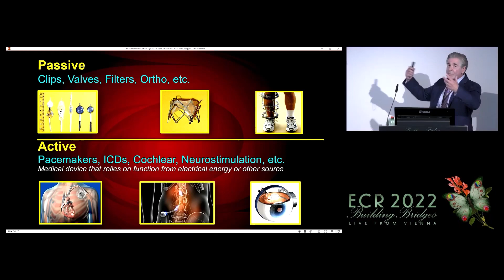So these are the factors that impact passive implants when you're scanning with vertical field MR systems. First and foremost, we need to give attention to the field strength. So is it 1.2 Tesla or is it 0.2 Tesla? Then realize that the direction of the static magnetic field is different than what we have on a horizontal bore system. And then finally, there's the spatial gradient magnetic field value. I'm going to talk more about that, but that's something that's presented in the labeling, where you will usually see a passive implant stated as tested at 1.5 and/or 3 Tesla, and then the highest spatial gradient magnetic field that was used to establish the force information for that implant.